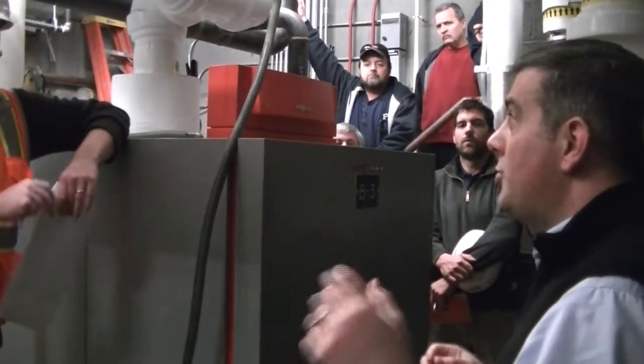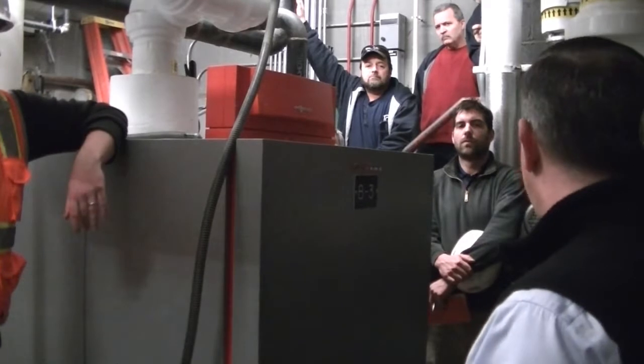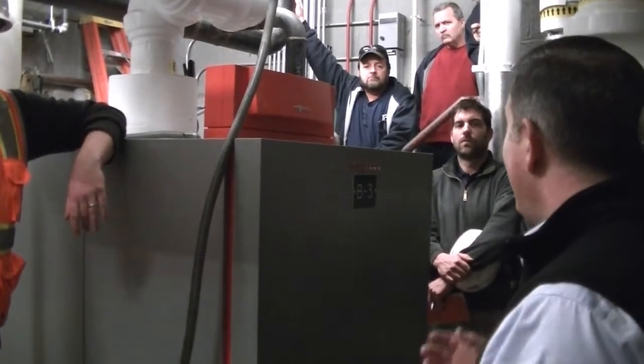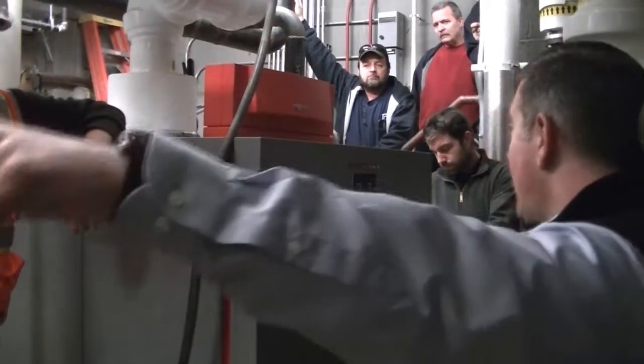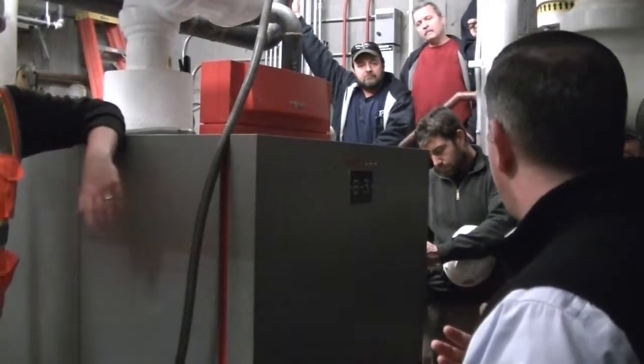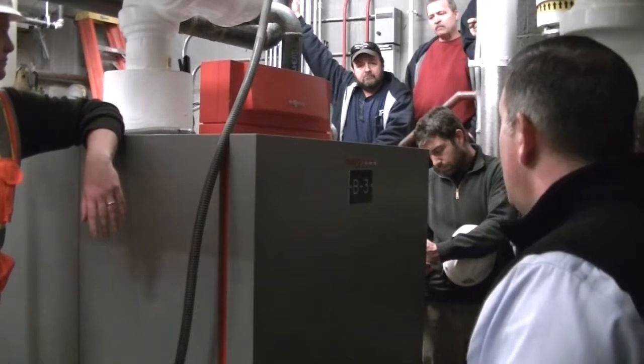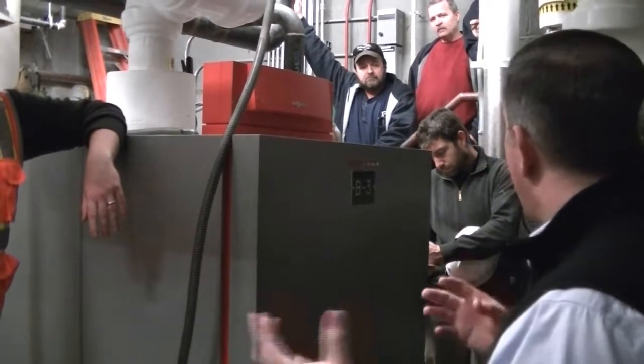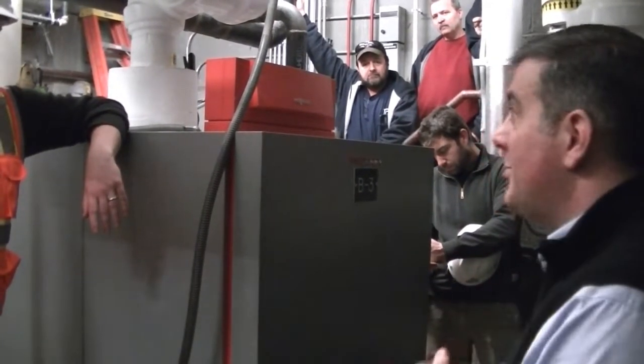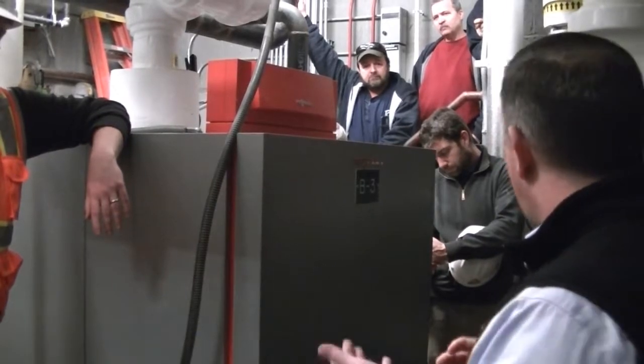We've set up boiler 2 in our system to always be the lead boiler. Okay? I couldn't make it boiler 1 because boiler 1 has to have the cascade control on it. Oh, so that's the reason for the number. Even though it's boiler 2, it's first stage heat. Right. So all we've done is program boiler 2, which is your cogen system, to be the lead boiler all the time. So that one comes on first.